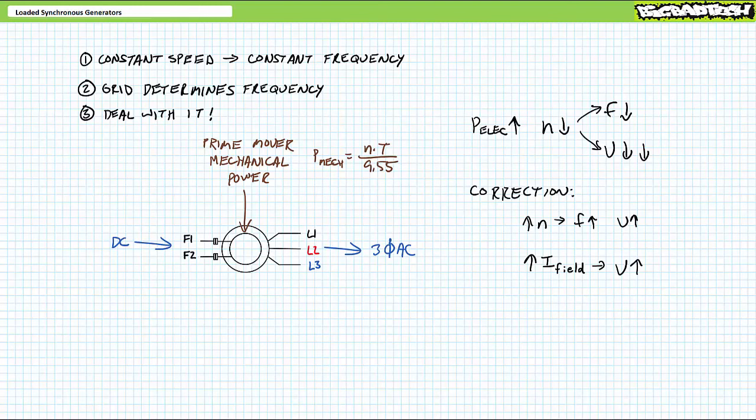In conclusion, we examine synchronous generators in the loaded condition. Learn that the magnitude and reactive nature of an electrical load can influence voltage magnitude. Due to non-ideal components internal to stator windings, both resistive and inductive loads experience output voltage reduction as a function of load current, with this voltage reduction being more pronounced for inductive loads. Capacitive loads, in contrast, experience greater output voltage as a function of load current. Generator operators compensate for these load-induced voltage changes by increasing and decreasing field current to meet the desired voltage specification.